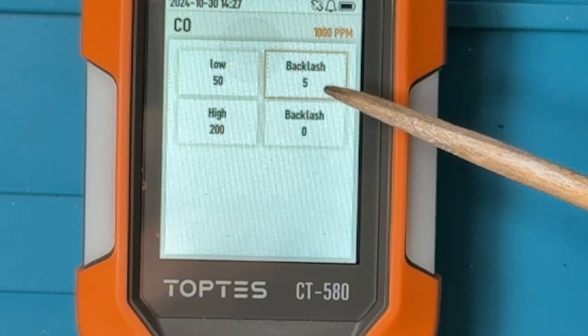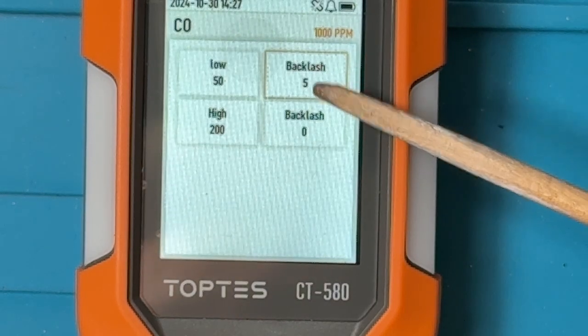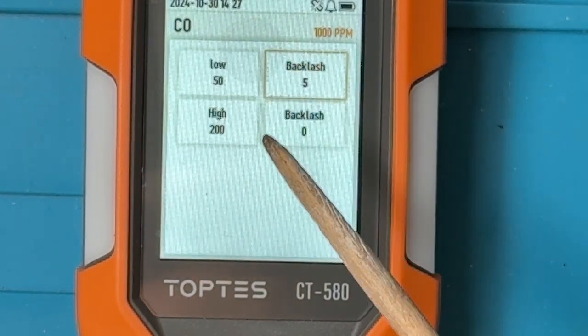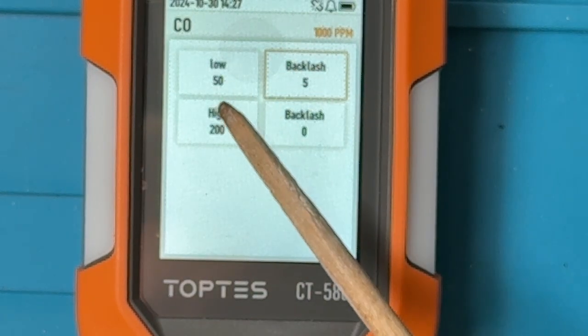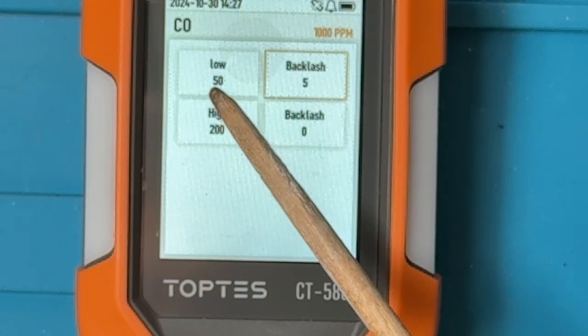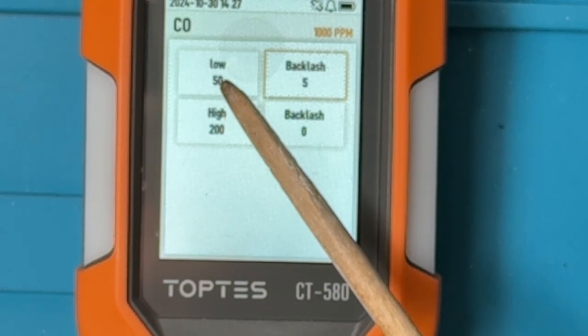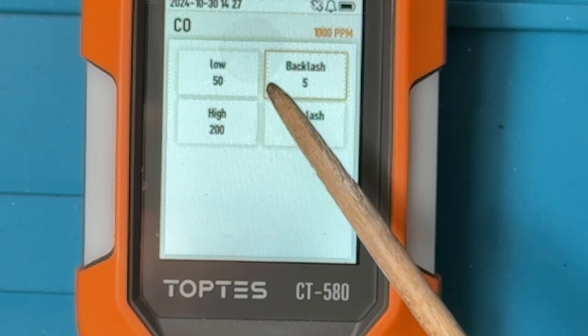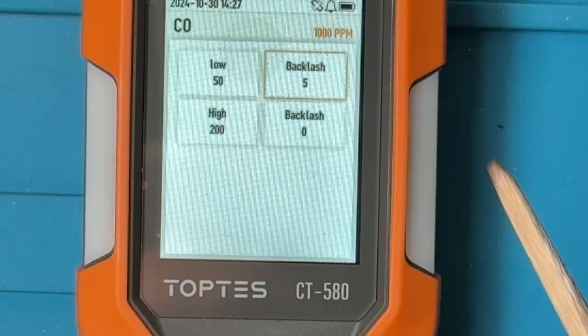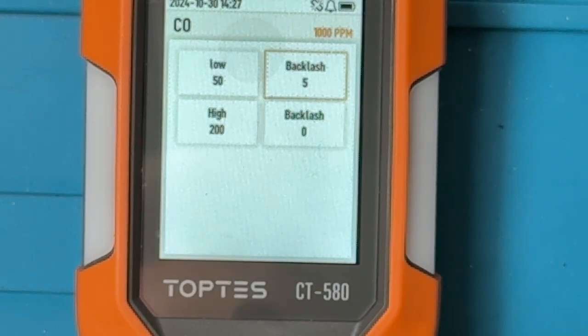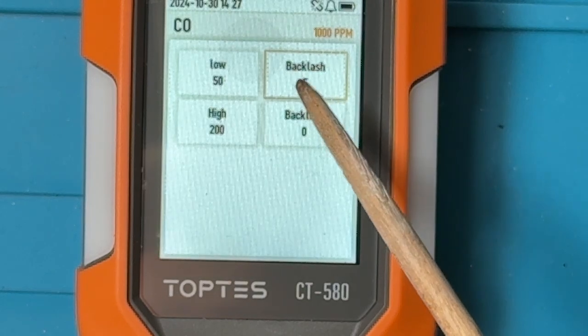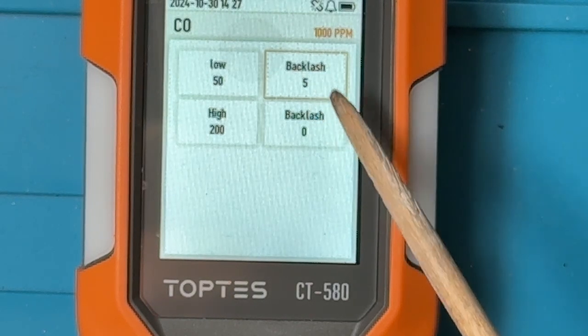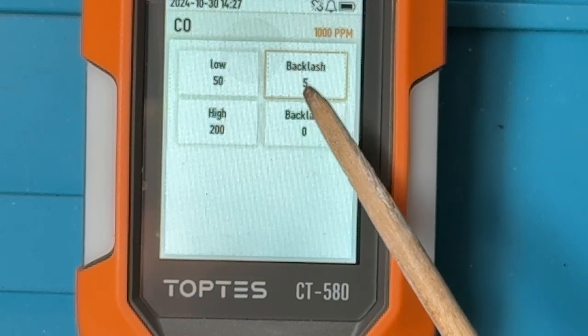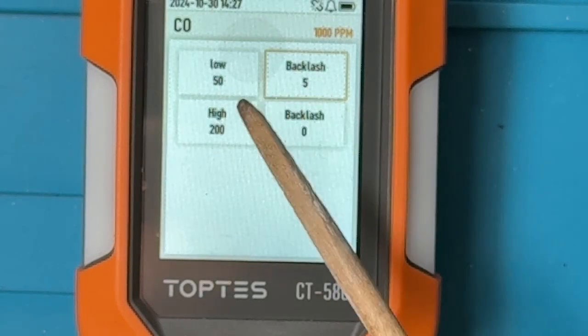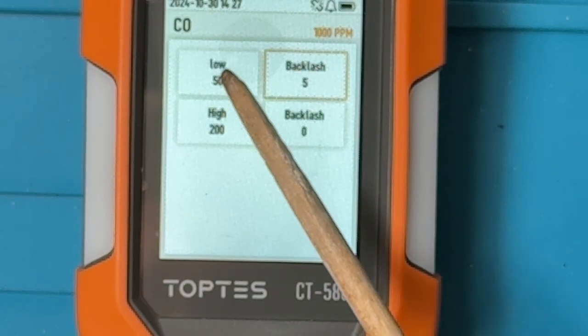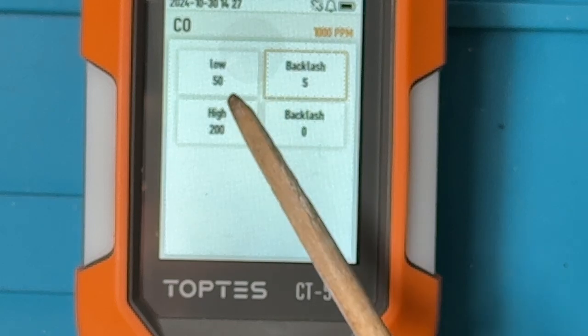Okay, and now you can see that there's a backlash value of 5 entered here. What that means is that the low threshold alarm will sound when we reach a level of 50 or above, but the alarm will keep going off even if we reach a level of 45, 49, 48. So it has to drop at least 5 units, because that's what we've put in here as backlash. It has to drop 5 units below this threshold. So in this case, the threshold being 50, 5 units below would be 45.